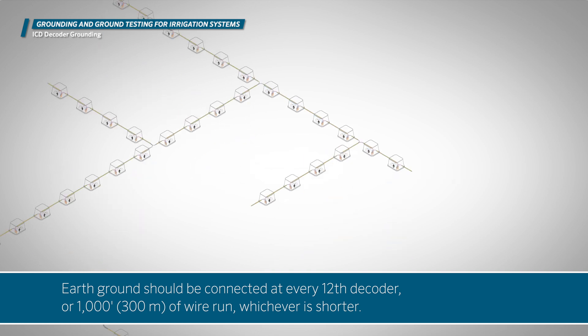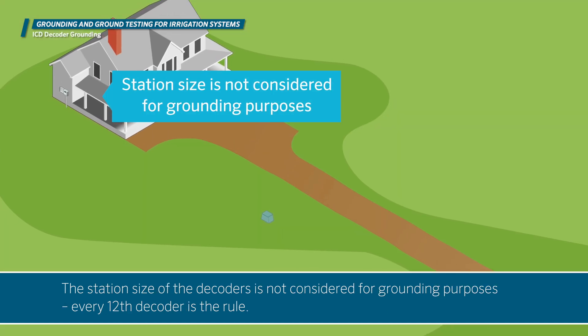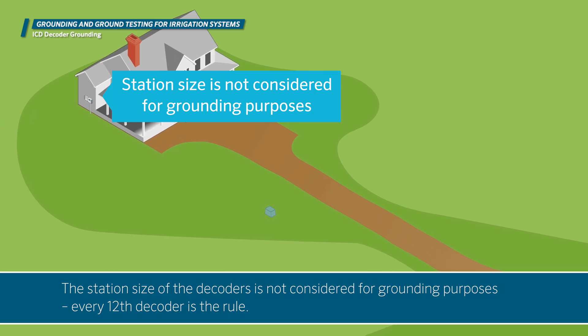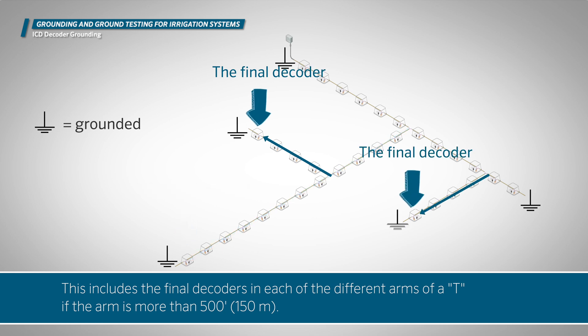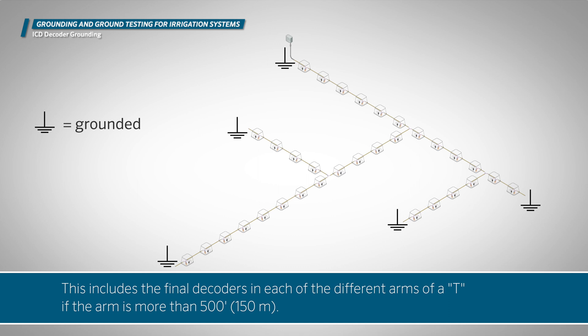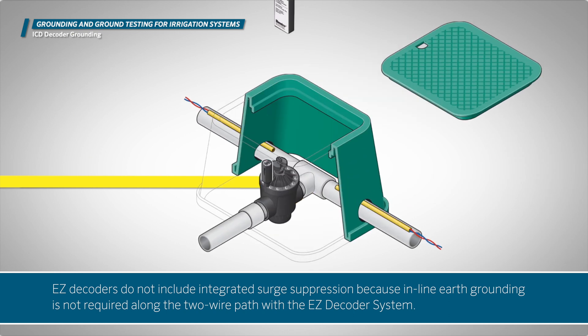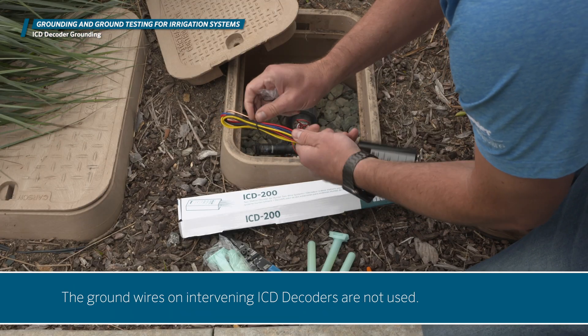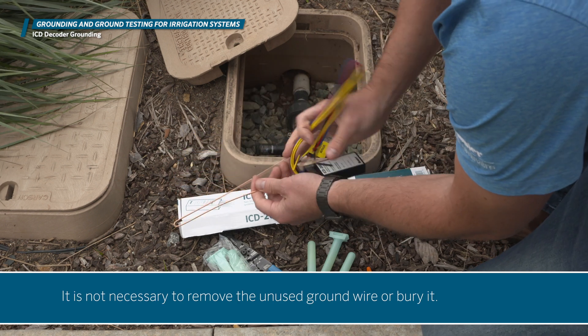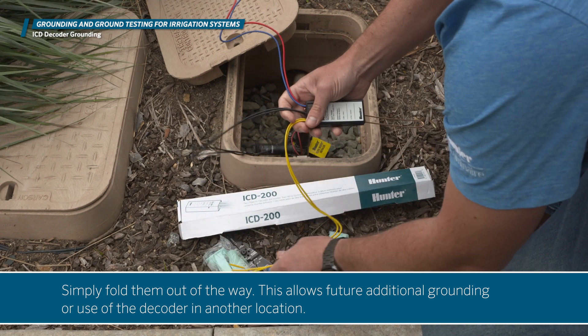Earth ground should be connected at every 12th decoder or 1,000 feet (300 meters) of wire run, whichever is shorter. The station size of the decoders is not considered for grounding purposes — every 12th decoder is the rule. The final decoder in any wire run should be grounded, including the final decoders in each arm of a T if the arm is more than 500 feet (150 meters). EZ decoders do not include integrated surge suppression because inline earth grounding is not required along the two-wire path. If you're in a high lightning area, you can use the Dual-S surge arrestor with EZ decoders. The ground wires on intervening ICD decoders are not used and it is not necessary to remove or bury them — simply fold them out of the way. This allows future additional grounding or use of the decoder in another location.